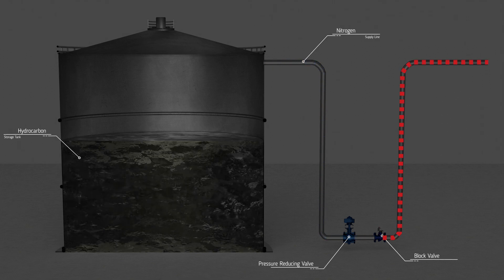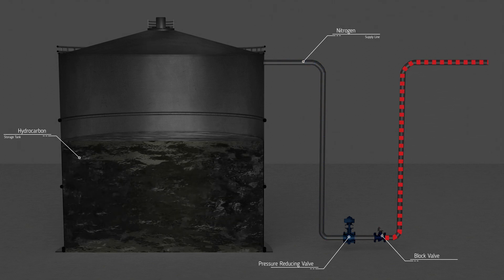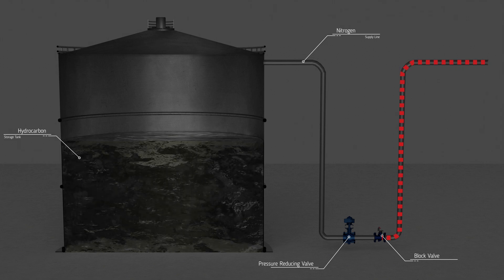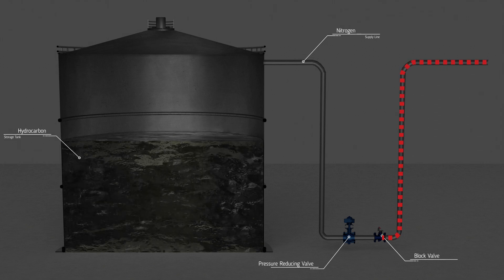Six months before the explosion, the manager had personally checked that the nitrogen blanketing was in operation, but no later check had been carried out.